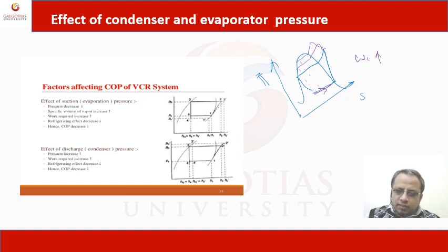The compressor work is increasing, the cooling effect is decreasing. So ultimately, what about the performance? The performance is the refrigeration effect divided by the compression work. If the cooling effect decreases and the compression work increases, the overall COP will decrease. So there is no advantage in increasing the condenser pressure. We need to maintain the condenser pressure as per the required COP and required cooling effect.